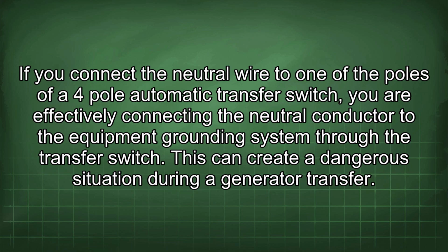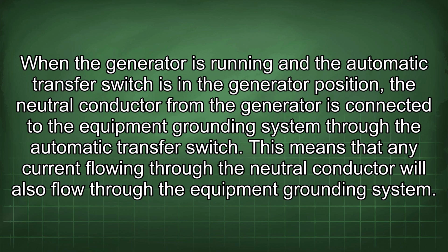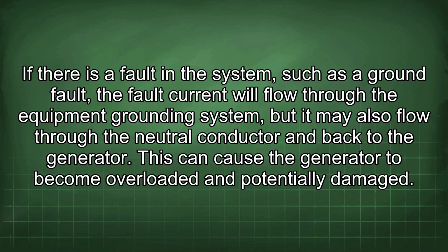This can create a dangerous situation during a generator transfer. When the generator is running and the automatic transfer switch is in the generator position, the neutral conductor from the generator is connected to the equipment grounding system through the automatic transfer switch. This means that any current flowing through the neutral conductor will also flow through the equipment grounding system. If there is a fault in the system, such as a ground fault, the fault current will flow through the equipment grounding system, but it may also flow through the neutral conductor and back to the generator. This can cause the generator to become overloaded and potentially damaged.